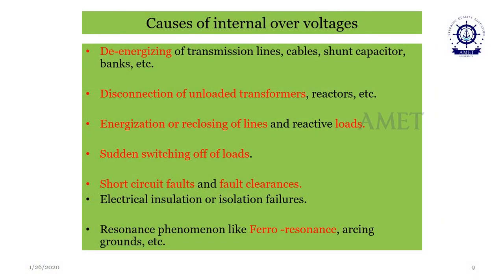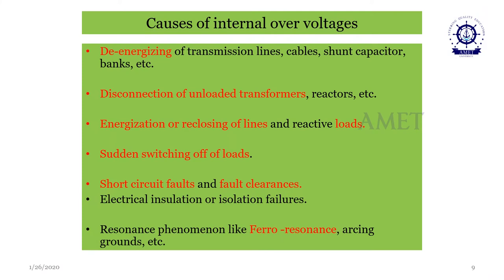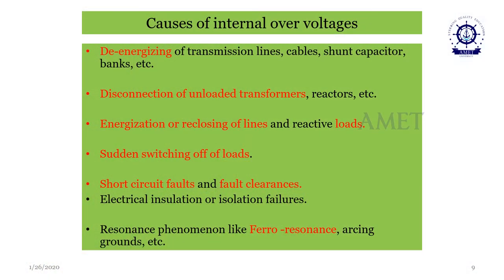As I said before, these internal overvoltages are originated inside the network or the system, and it's mainly due to de-energization of transmission lines, cables, shunt capacitors or capacitor banks, and disconnection of unloaded transformers and shunt reactors. Energization or reclosing of circuit breakers or extra high voltage transmission lines, sudden switching of loads, inductive loads or capacitive loads, then short circuit faults, say unsymmetrical faults or fault clearances. During clearing of the faults, an internal overvoltage may occur. Then electrical insulation and isolation failures.